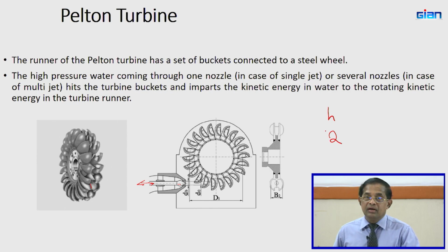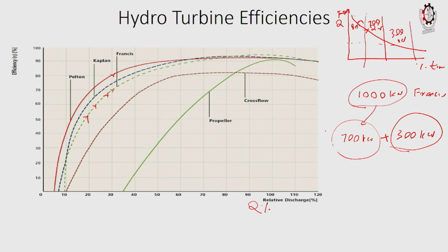And also there are issues like, even though we say this efficiency, the manufacturer will say the efficiency curve is this, right, but it is very difficult to measure this at the site. At the site, how to measure these efficiencies for verification is very complicated. Even if he claims his machines have 90% efficiency, to test it and confirm it at site is very difficult.